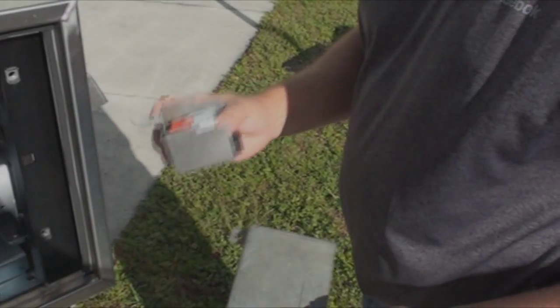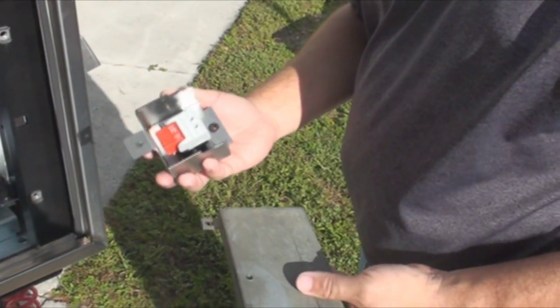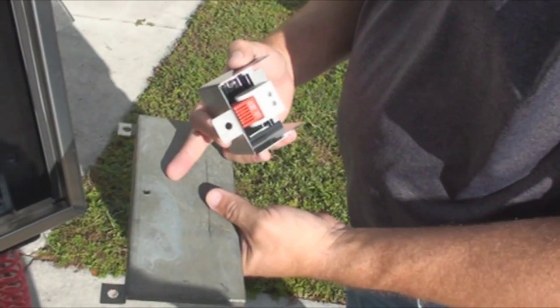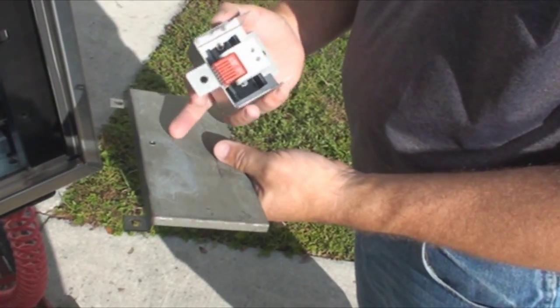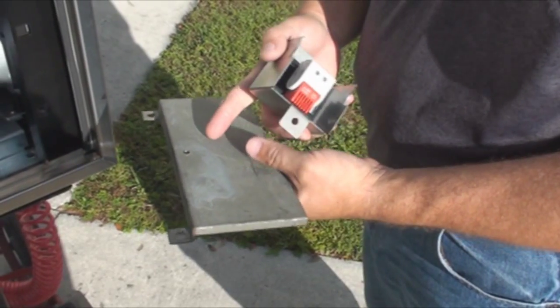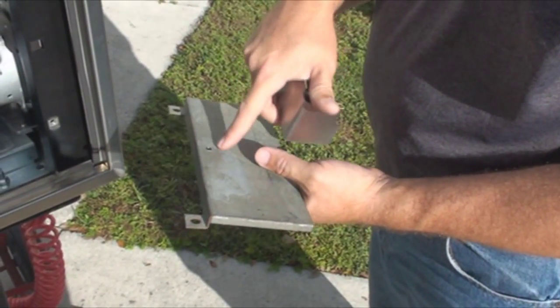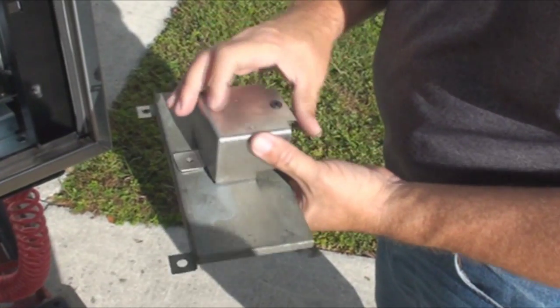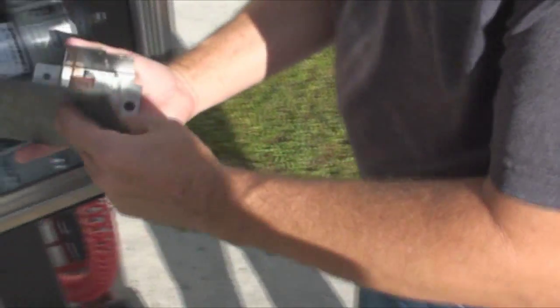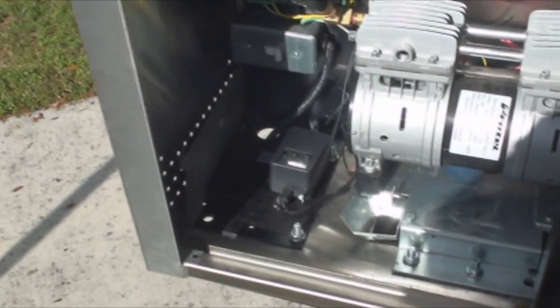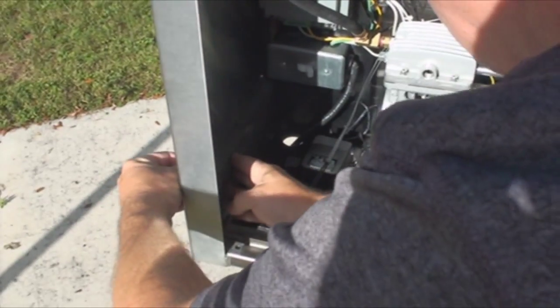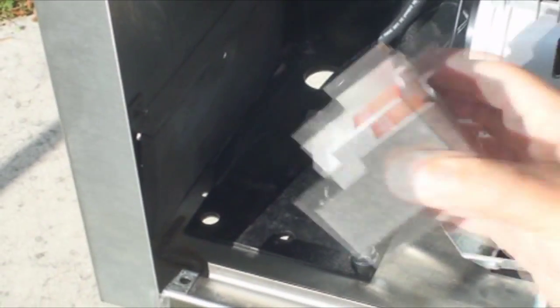The next step will be to install the thermostat and the thermostat bracket on the lower vent blocker plate. This plate is provided by TPI. You'll have to drill a hole for the mounting screw, and that's best done if you put the bracket in the enclosure, temporarily install a screw so that it's at the right location, and then hold the thermostat bracket in place and mark the center line for the hole.